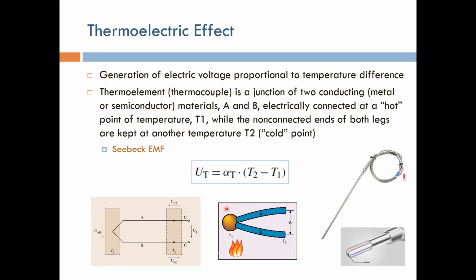This type of sensor can be used at extremely high temperatures, so the junction point can be in the thousands of degrees Celsius or Kelvin, while the reference point is usually at room temperature or some other much lower reference temperature. You can use a thermocouple, a thermistor, or an RTD to measure the reference temperature, while the junction might be in a furnace or sterilizer with very high temperatures.